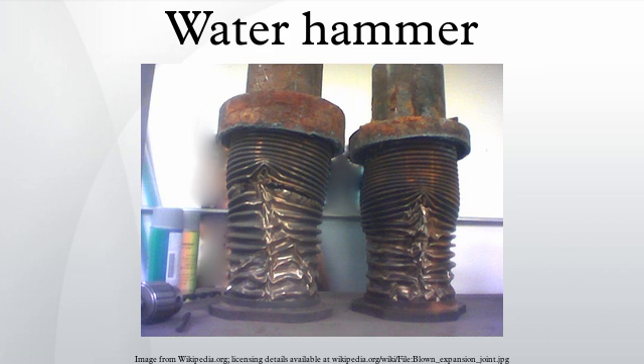The liquid either side of the vacuum is then accelerated into this space by the pressure difference. The collision of the two columns of liquid results in cavitation and causes a large and nearly instantaneous rise in pressure. This pressure rise can damage hydraulic machinery, individual pipes and supporting structures. Many repetitions of cavity formation and collapse may occur in a single water hammer event.